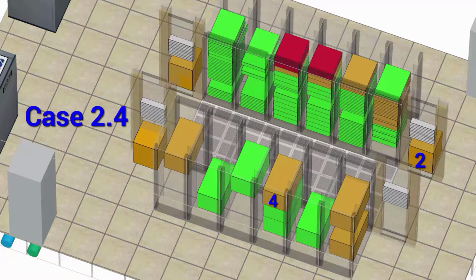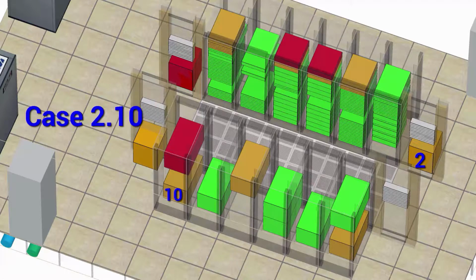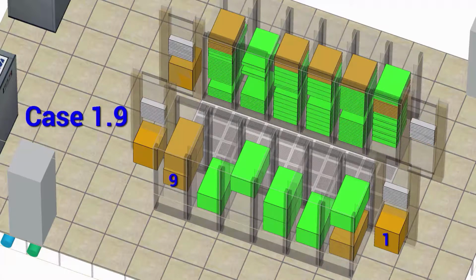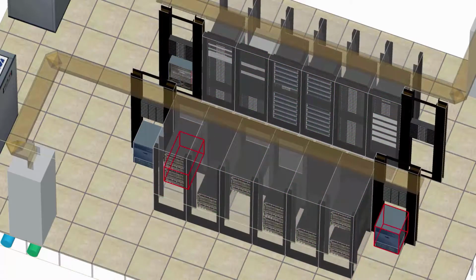This accurate simulation of a physical change prior to its application in the physical data center is invaluable. By use of the virtual facility, the IT group can make the best deployment decision with respect to the data center environment. This example has predicted case 1.9 as the best option. As you can see, this is the only scenario out of 20 that resulted in 0 IT equipment outside of the ASHRAE allowable temperature ranges. Only with predictive analysis using the virtual facility can you know the best result.